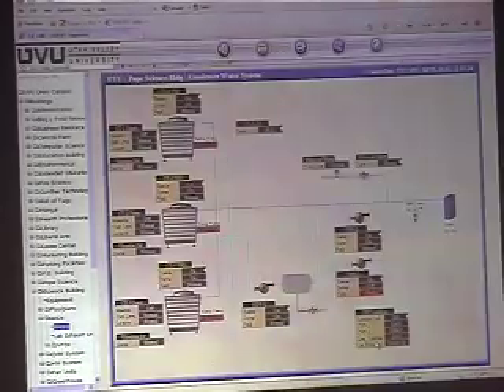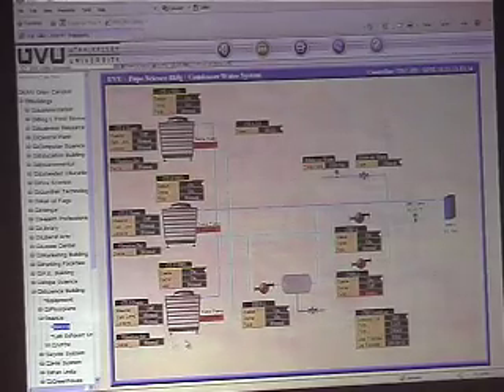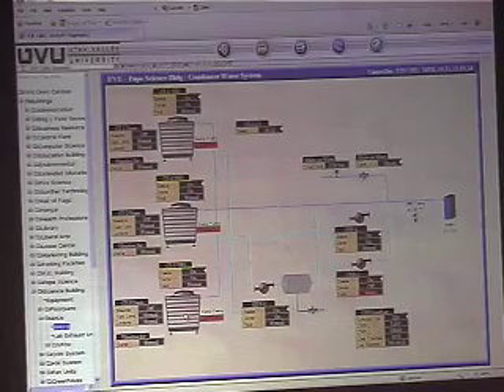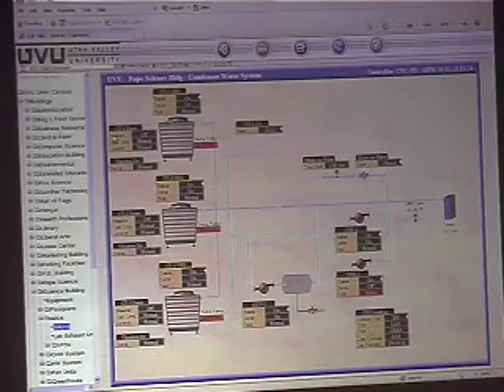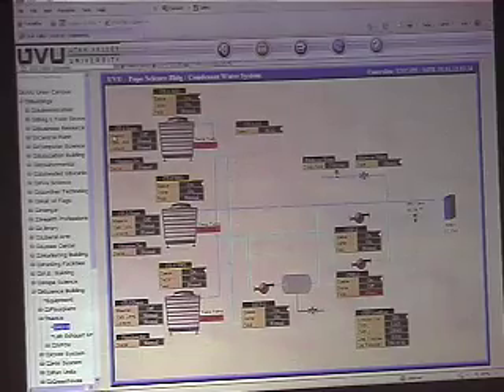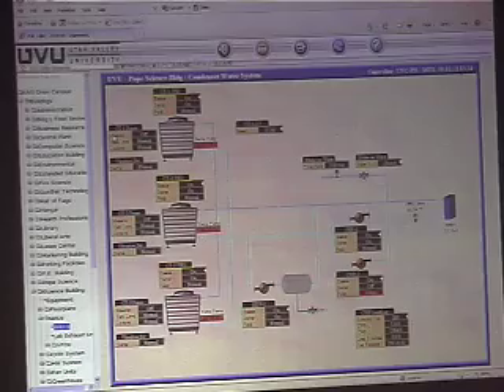Then your condenser water coil here is fed from this equipment. So you've got your 3 cooling towers here. They operate simultaneously. It's basically one big unit. Each one of them has its own level sensor system on it. So it's basically one of those systems that, did they do the cooling tower training already? Did they go over how those sensors are set up in there? They've got the probes inside the pipe.